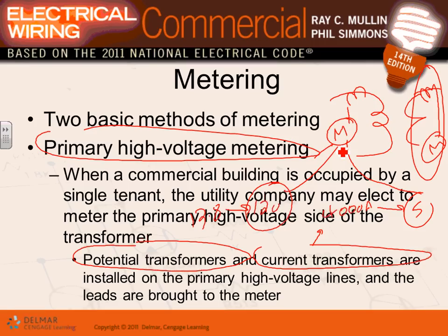Yes, Adam? I thought you said that's a high voltage meter. It can be on the high voltage or on the low voltage. Same. I'm just showing it on the high voltage side. The high voltage is where you put your CTs here. If you put it here, that's high voltage. If you put them here, it's low voltage. The meters themselves, Adam, they always work on low voltage. Otherwise, they'll burn them. Always. All meters work on low voltage.